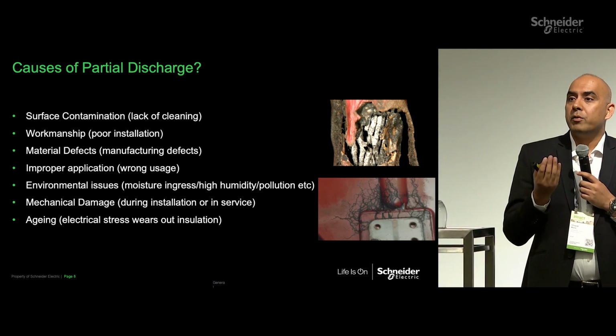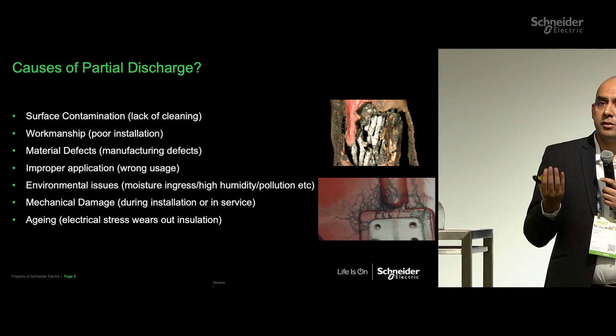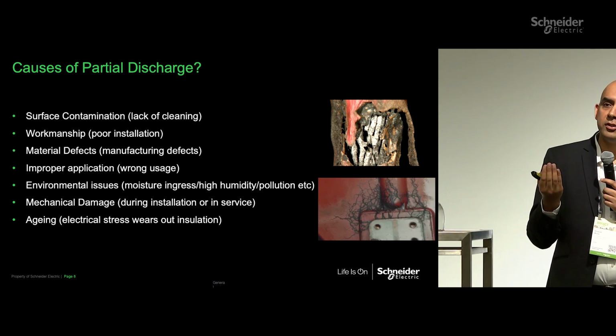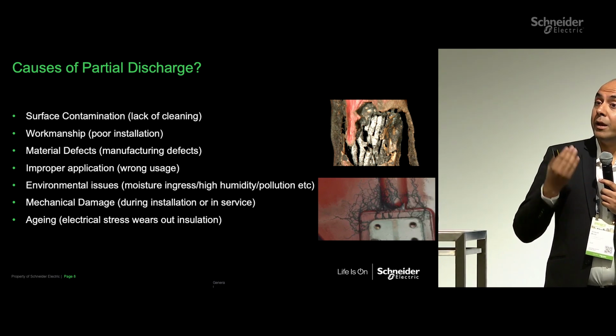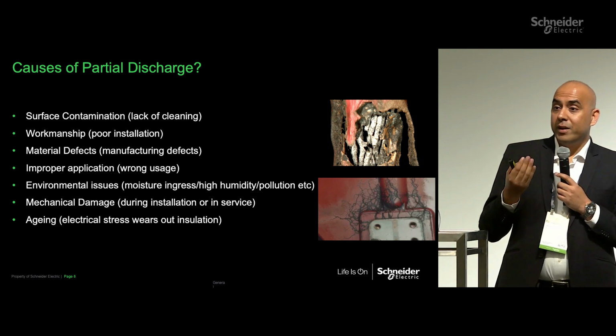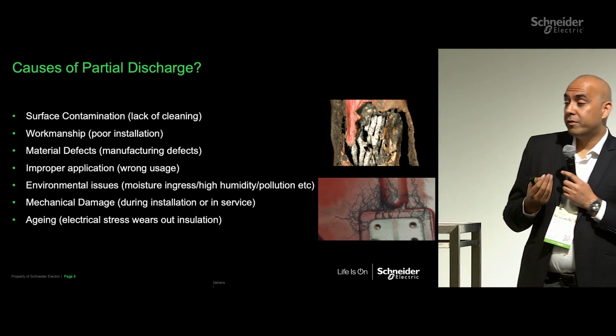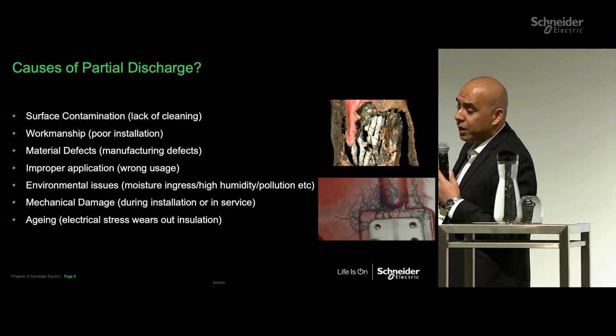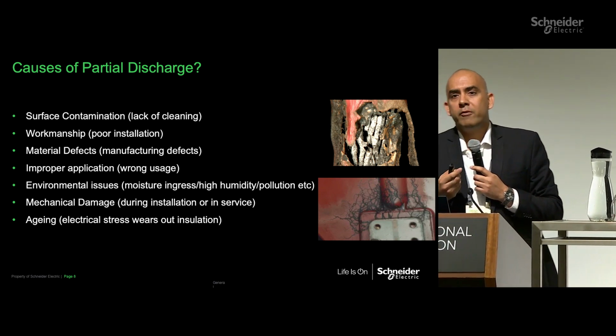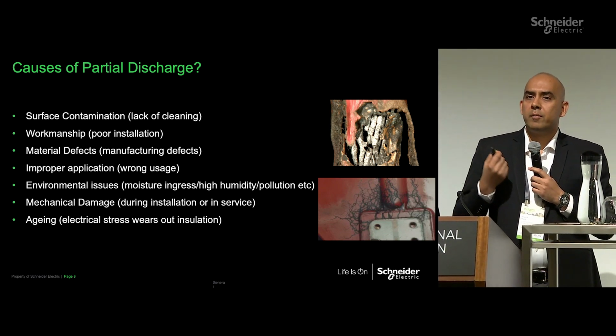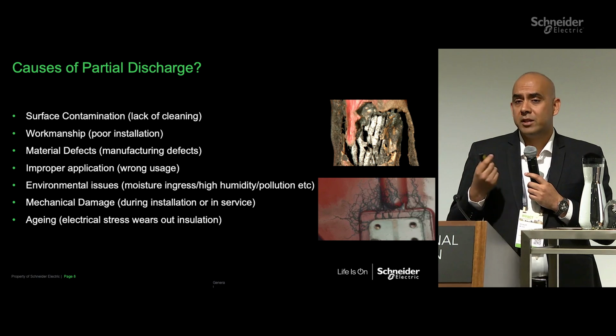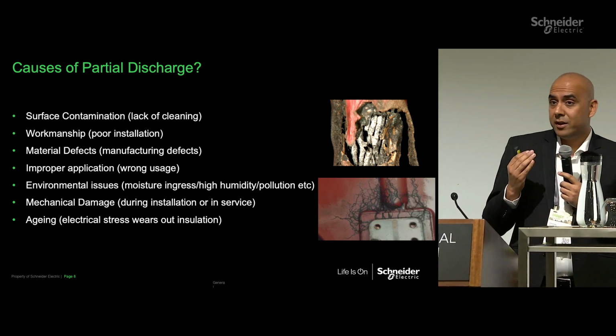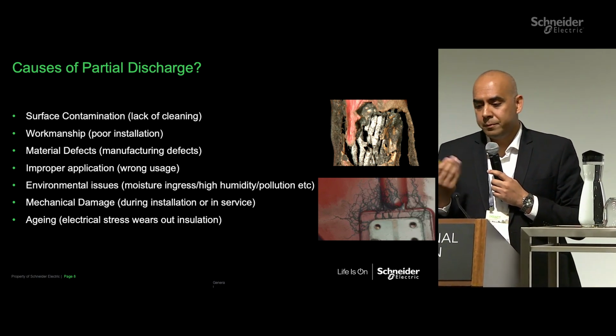And you've heard about cable termination failures in systems, and many times during installation, if the termination of cable is not proper, you could have these issues coming from day one. And that's why we recommend that this is something which should be monitored very closely. There could be manufacturing defects. Obviously, with very strong standards now from IEEE, and even the Australian standards are very strong on this, the risk is much lesser, but yes, it can happen.